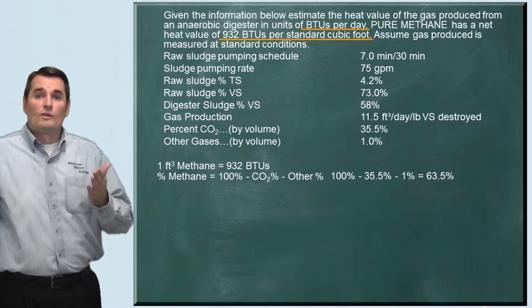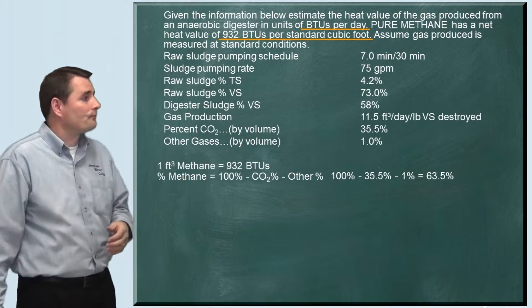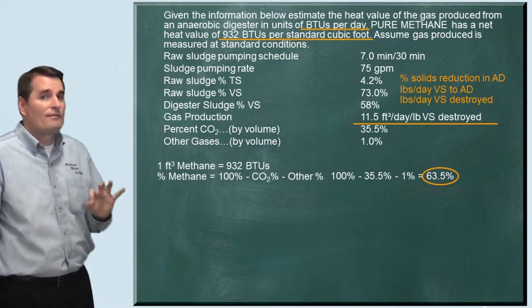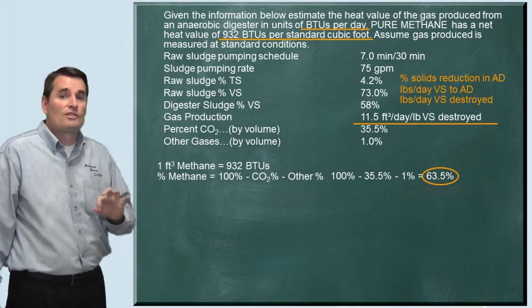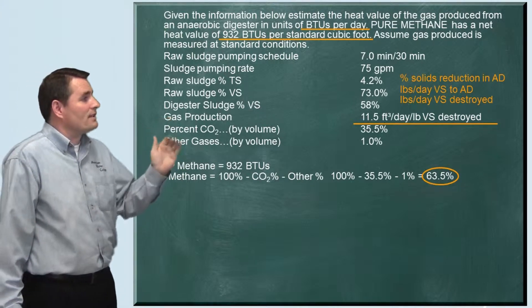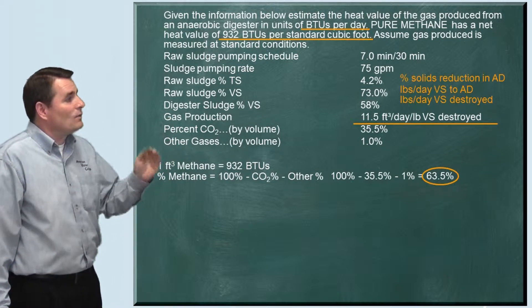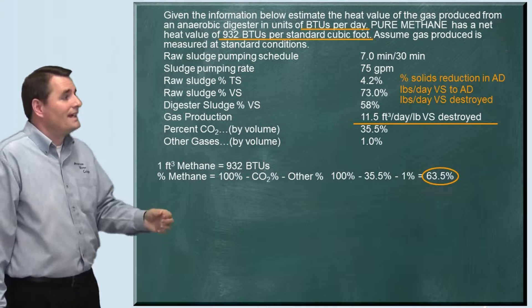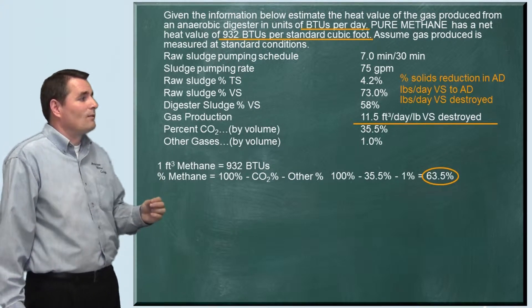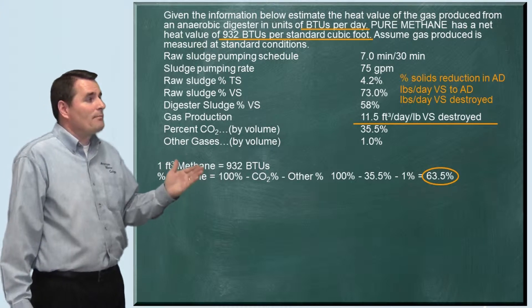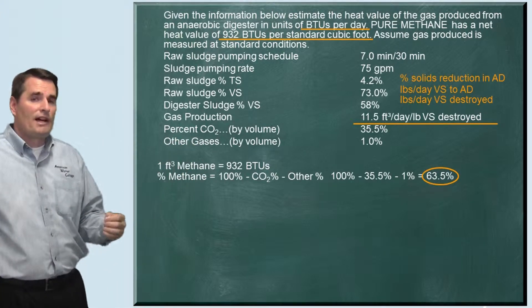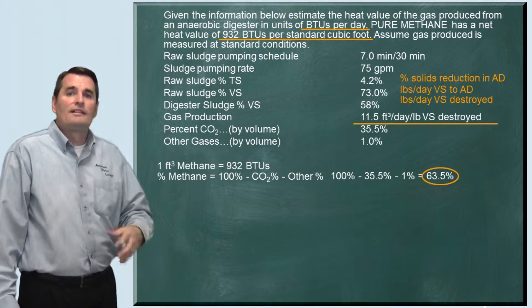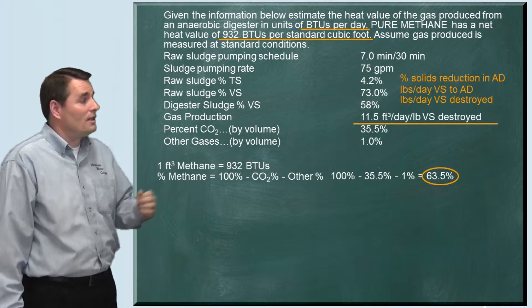That's important because we're trying to calculate the heat value from this methane. There are three major steps to solve this problem: first, find the percent solids reduction in the anaerobic digester; then calculate how many pounds per day of volatile solids are sent to the digester; and finally calculate how many pounds per day were destroyed. Once we know pounds per day destroyed, we use the 11.5 cubic feet per pound factor to calculate methane and then the overall heat value.